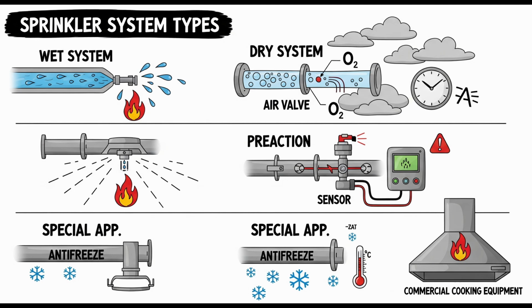What about sizing these systems? How big can they be? For single and non-interlock pre-action systems, the size limit is based on the number of sprinklers. Not more than 1,000 sprinklers can be controlled by a single pre-action valve. Okay, just a simple sprinkler count limit for those two types. And double interlock, is it different? Yes, double interlock sizing is more involved, much like dry pipe systems, because managing the time delay to water delivery is crucial even after the valve trips. System size can be determined by one of four options.